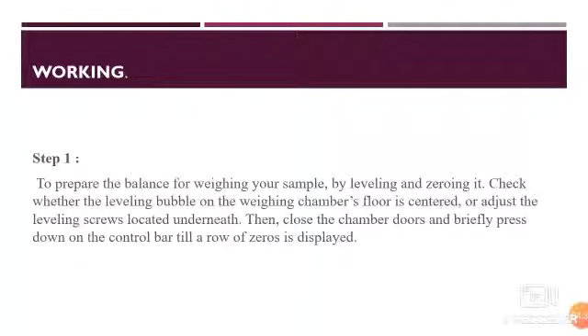Now, how does an analytical balance work? Step number one: prepare the balance for weighing your sample by levelling and zeroing it. Check whether the levelling bubble on the weighing chamber floor is centered, or adjust the levelling screw located underneath. Then close the chamber doors and briefly press down on the control bar until a row of zeros is displayed.